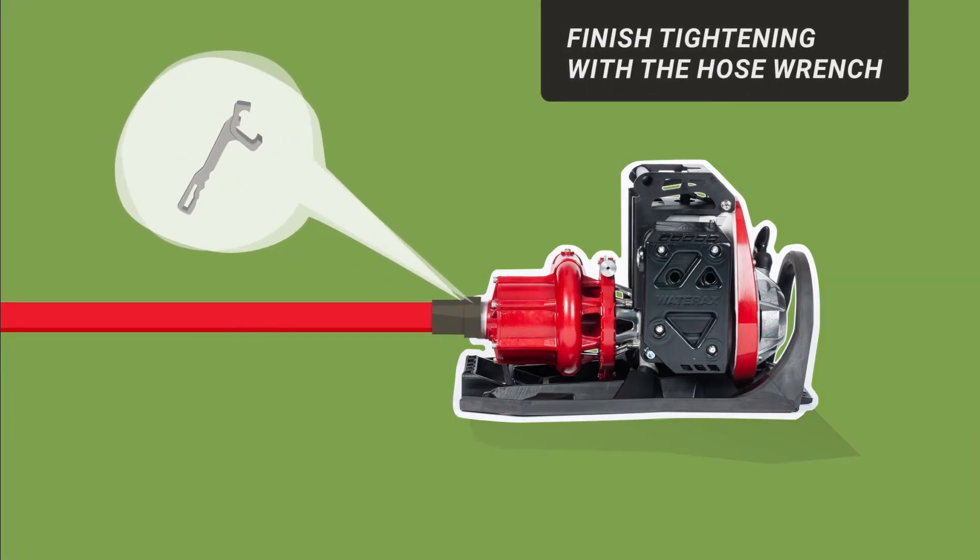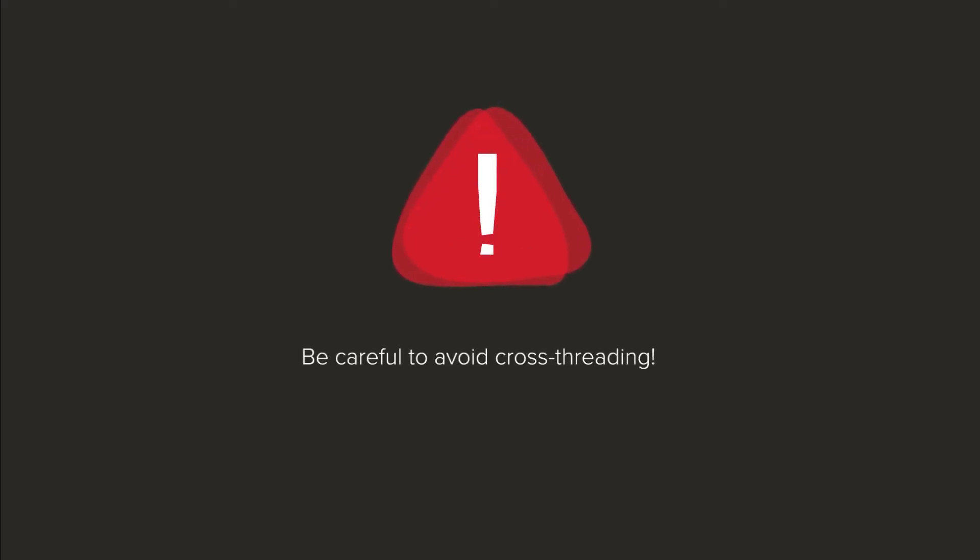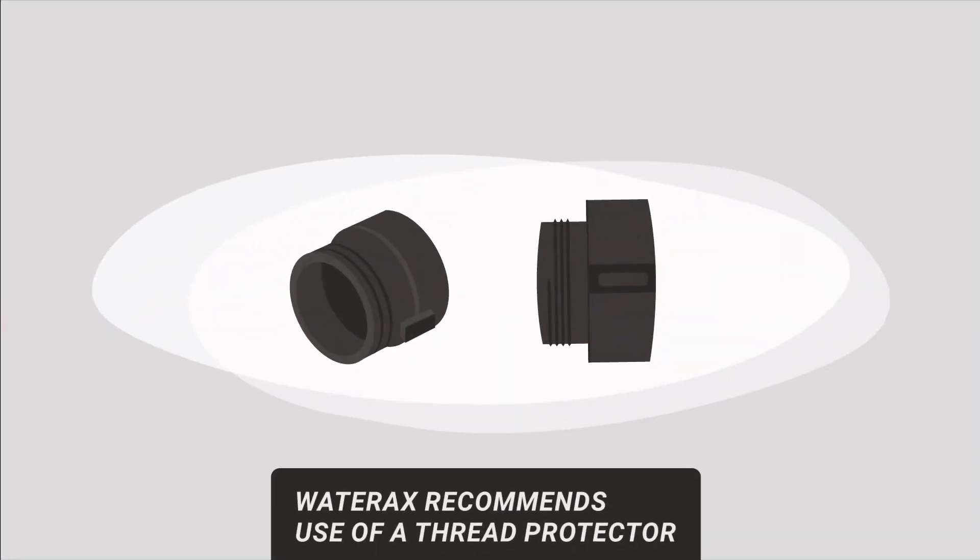Finish tightening with the hose wrench to prevent any air leaks. Cross threading can damage the connection and create air leaks that lead to air locks and potential pump end seizure. Waterax recommends the use of a thread protector to protect the pump end threads against any damage.